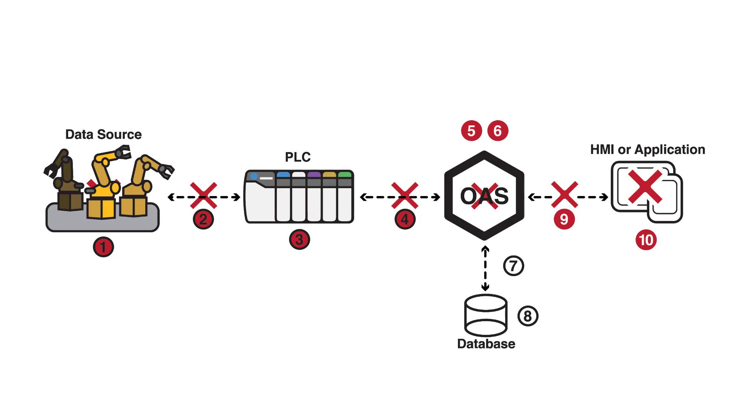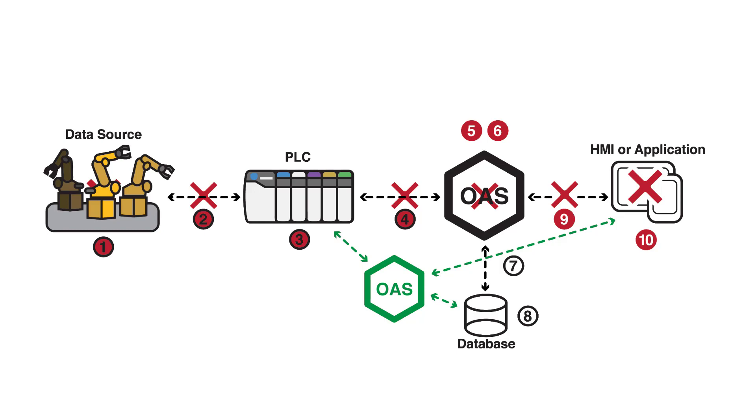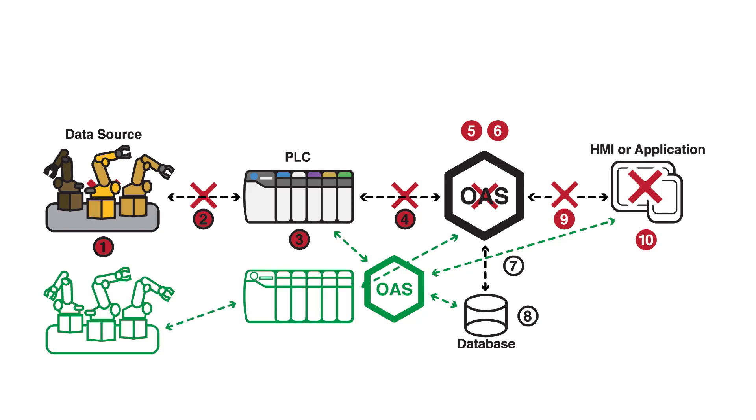But if we implement a second OAS engine with the same tag names in the second OAS engine, we can use a simple-to-use feature that the application can automatically switch to the backup node. Also, in the scenario where the data source is not available due to the controller or communications to the sensors, we can have a physical redundant path direct to the data source as well. The feature I'm going to show you will account for all of these failure scenarios.